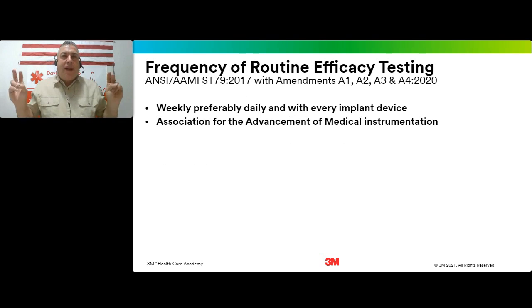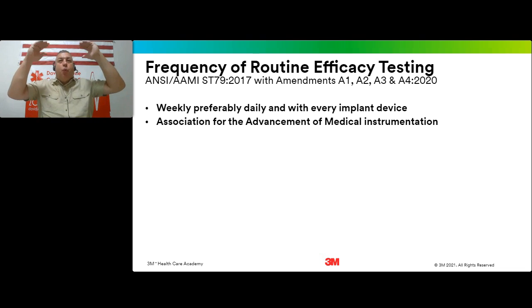AAMI has a very big section on moisture assessment within the document. Moisture assessment in AAMI means wet packs, okay? So if you look in the book and you look in the glossary or the index and you're looking for wet packs, you'll never see it. You got to look up moisture assessment. And AAMI has, again, these wonderful charts of what to do if there's a wet pack, how to chase that back, what the potential was, and why did it fail, or why did you get wetness.